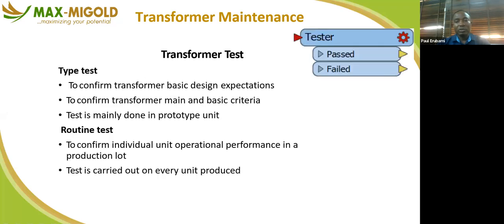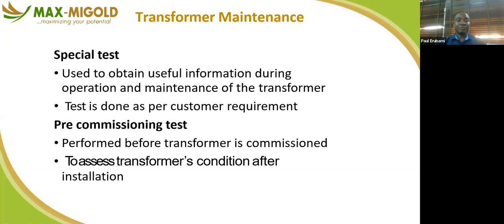So there are tests you need to take when working on your transformer. These are the tests to confirm the transformer's basic design expectation, to confirm the transformer's main and basic criteria. Tests are mainly done on prototype units. So we have routine tests to confirm individual units' operational performance in a production lot. So the test is carried out on every unit produced.